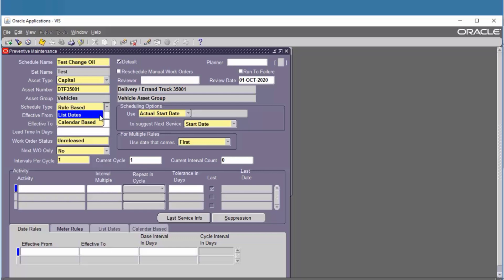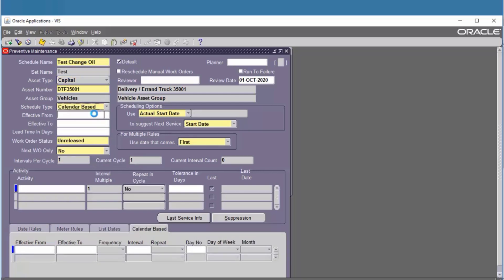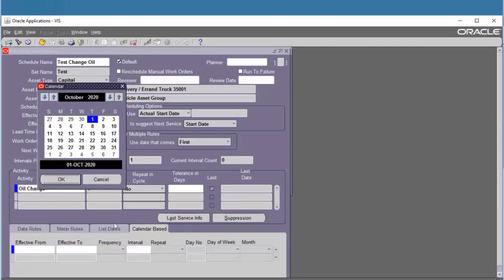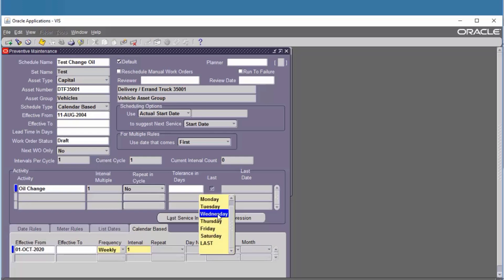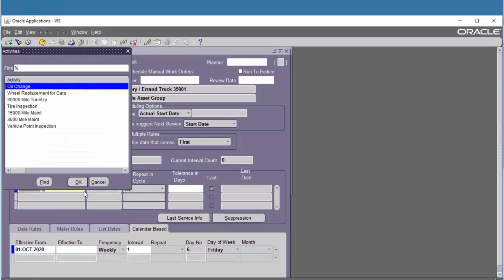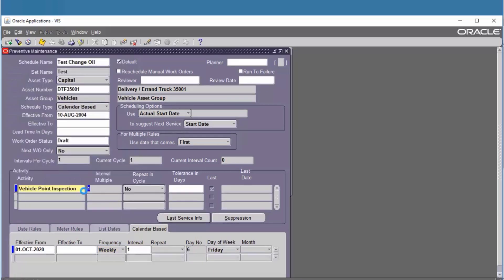Add update, work order status. Fill the activity, define the effective date from, choose the frequency — interval and day of week. Frequency: Weekly, Interval: 1, meaning there is one maintenance every week beginning on Friday. Save.